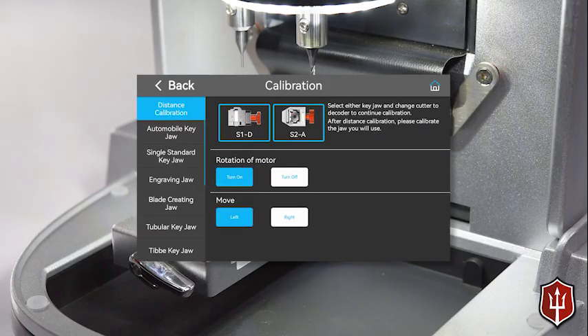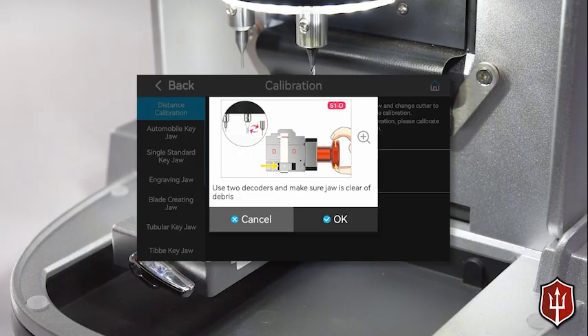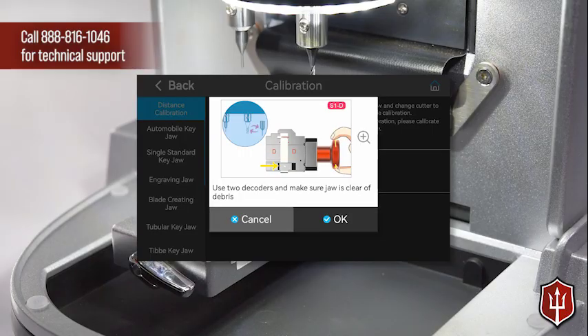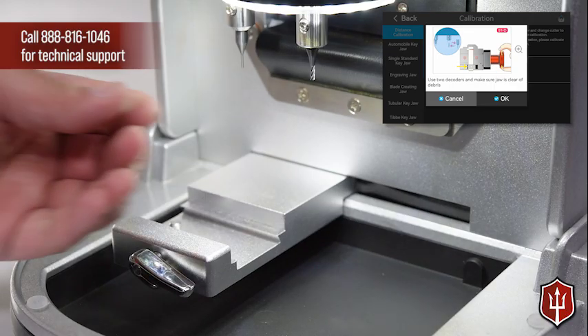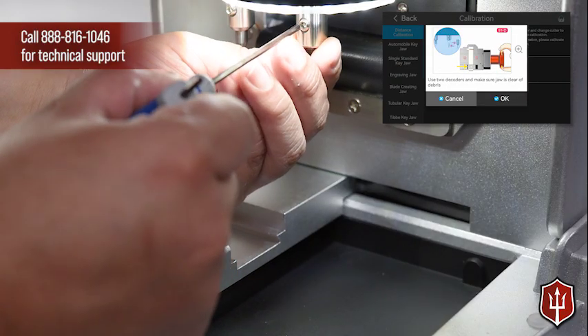On the distance calibration screen, choose one of the two available methods. You only need to complete one, depending on which jaws you have available. The first option uses the 4-way automotive and dimple jaw. For distance calibration, 2 standard decoders must be installed. If a cutter is installed, remove it and replace it with a decoder.